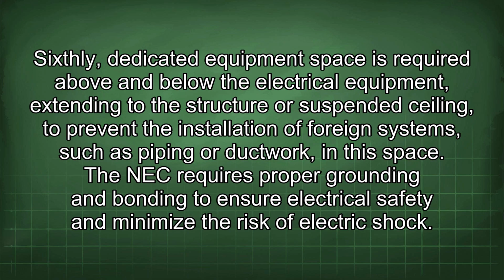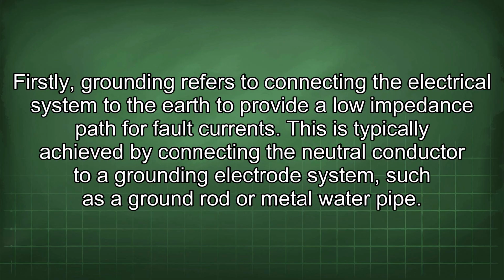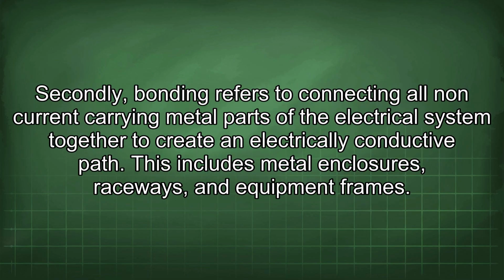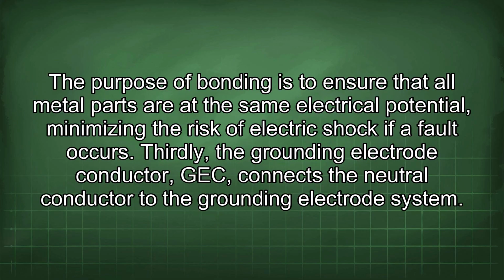The NEC requires proper grounding and bonding to ensure electrical safety and minimize the risk of electric shock. Firstly, grounding refers to connecting the electrical system to the earth to provide a low impedance path for fault currents. This is typically achieved by connecting the neutral conductor to a grounding electrode system, such as a ground rod or metal water pipe. Secondly, bonding refers to connecting all non-current carrying metal parts of the electrical system together to create an electrically conductive path. This includes metal enclosures, raceways, and equipment frames. The purpose of bonding is to ensure that all metal parts are at the same electrical potential, minimizing the risk of electric shock if a fault occurs.